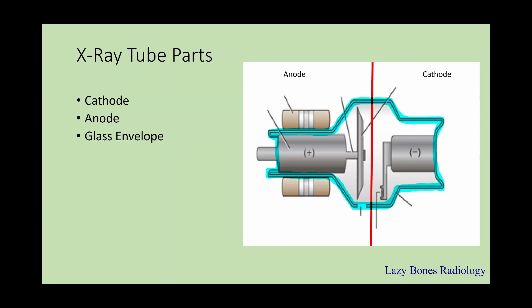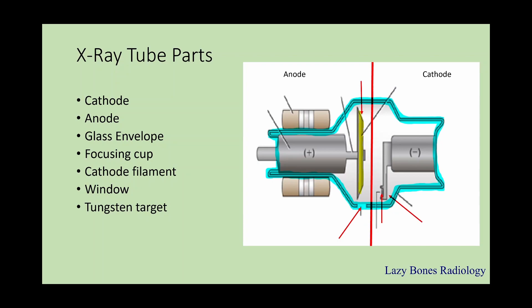Now let's talk about parts within the cathode: the focusing cup, and next is the cathode filament, which is within the focusing cup. On the anode side, there is the window, next is a tungsten target, and right behind it is the spinning anode, and lastly, the rotor. I'm briefly covering the different parts of the x-ray tube so you can have a basic knowledge of how the x-ray tube is set up.